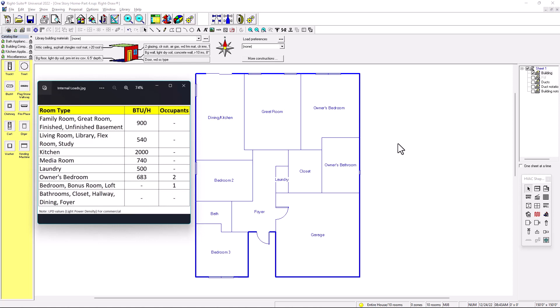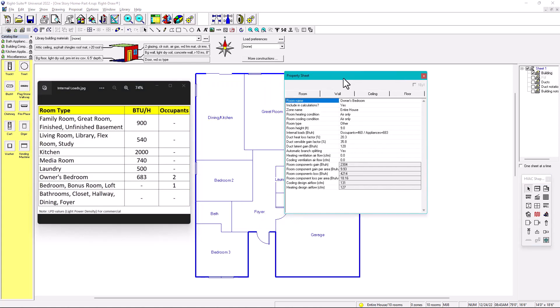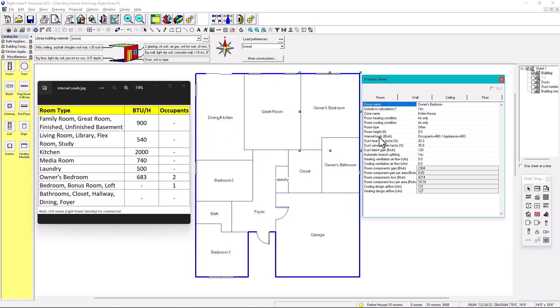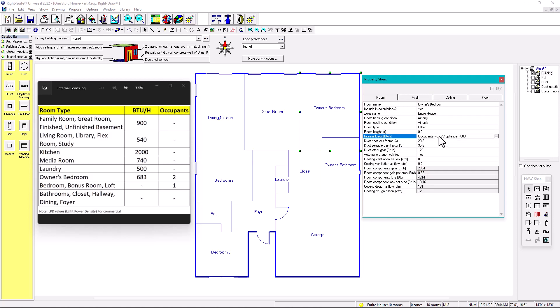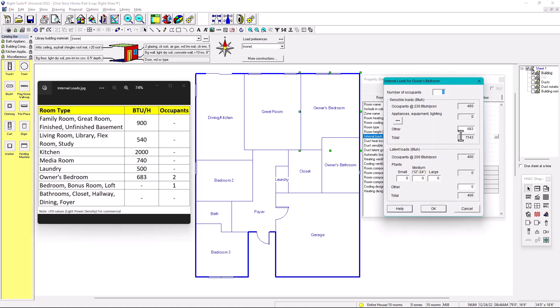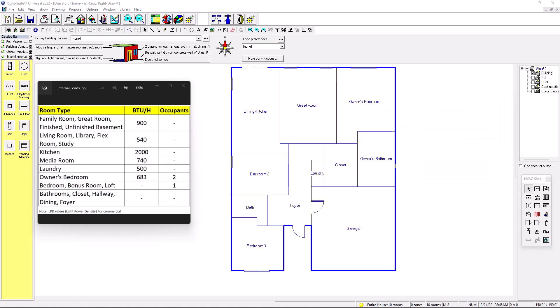To enter internal loads in the room layout, start with the owner's bedroom — right-click and open the property sheet. In the property sheet you'll see the internal loads section. Set the number of occupants to two, and in the 'Other' field enter 683. The occupant load shows 460 because the default is 230 per occupant times two. The appliance load shows 683.